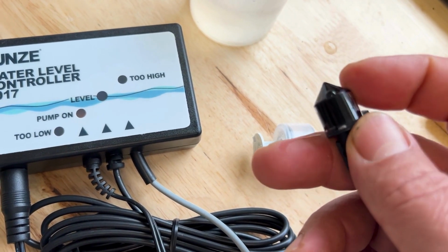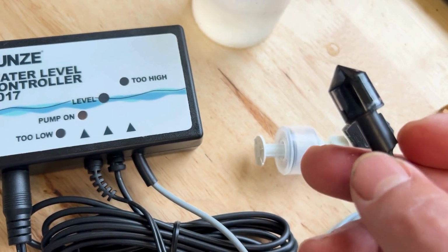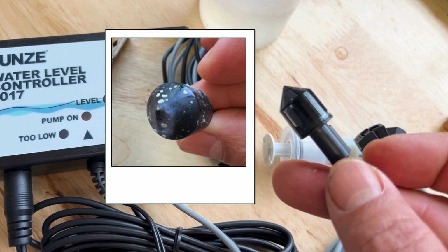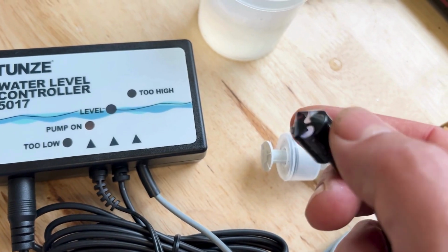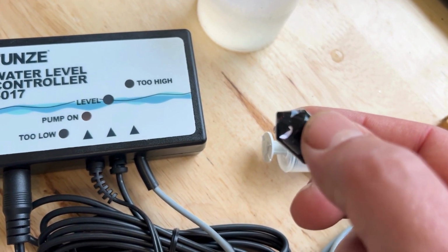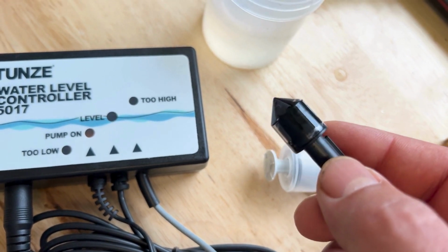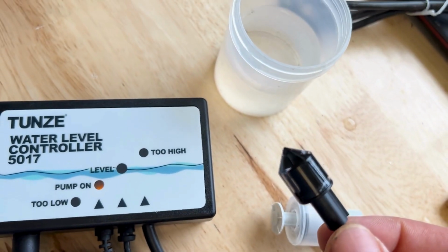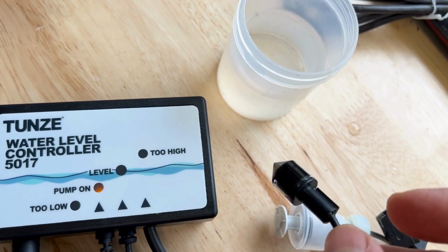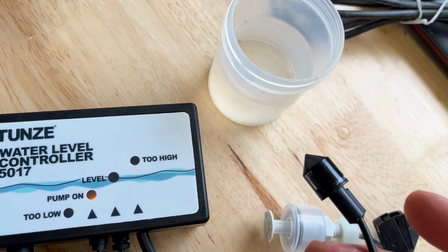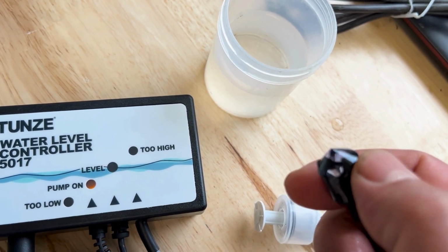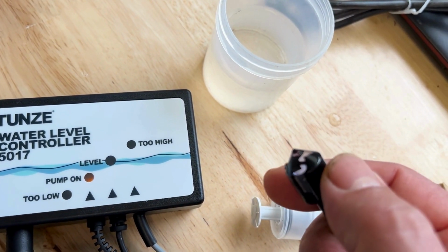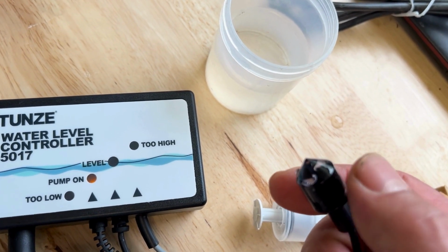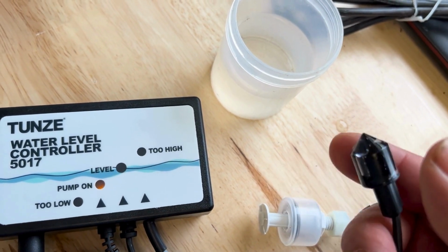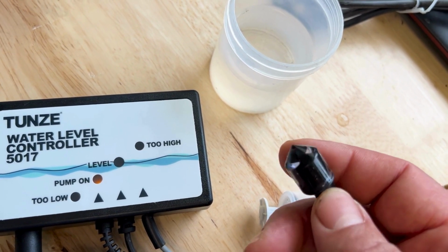Typically, the hazing we see is calcium deposits on this unit. I suggest white vinegar to clean them. It tends to work better than citric acid. It works faster. Citric acid tends to create, I guess it's a calcium citrate salt, that kind of forms a haze that's difficult to get off. If you use straight white vinegar, fill something about this size, maybe a shot glass, drop it in there for about an hour, and then just wipe it with a soft towel. This is plastic, so if you scrub it aggressively, scrape at it, scrub it with a Scotch-Brite pad or a magic eraser, you will scuff it and that will ruin the optic properties of the sensor.